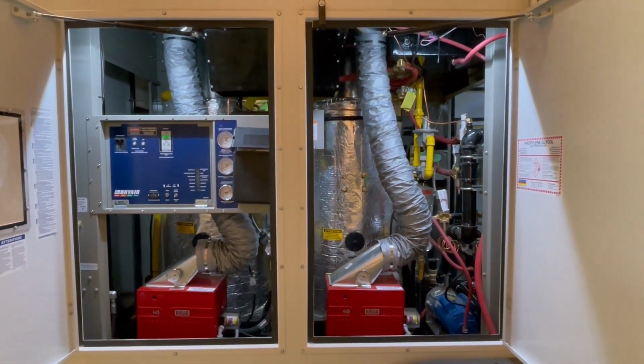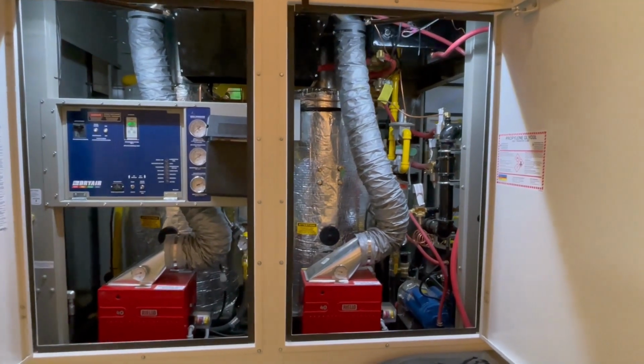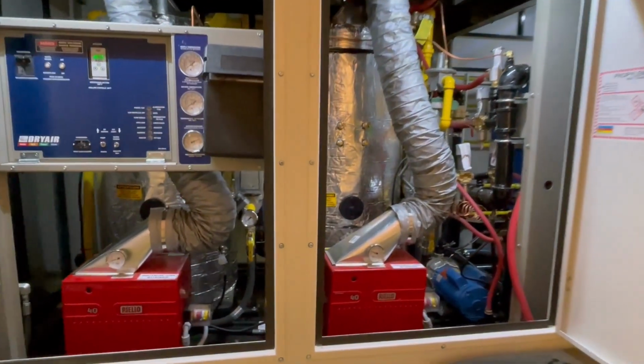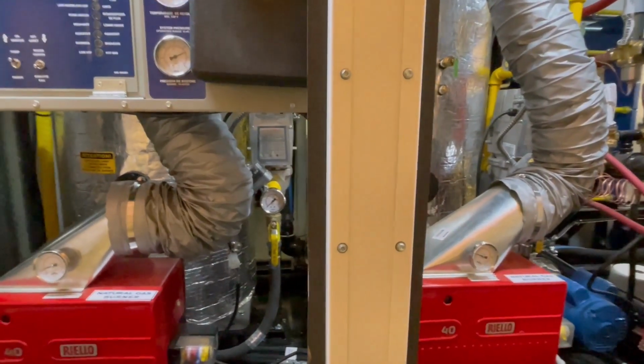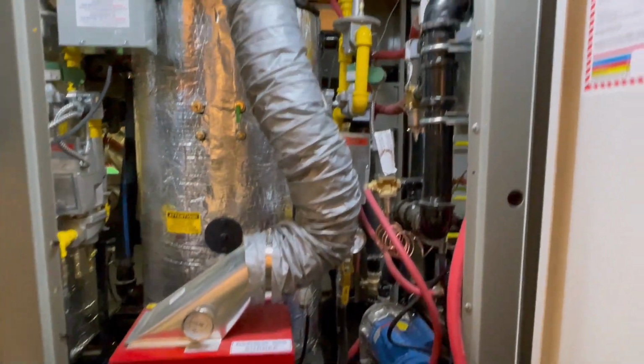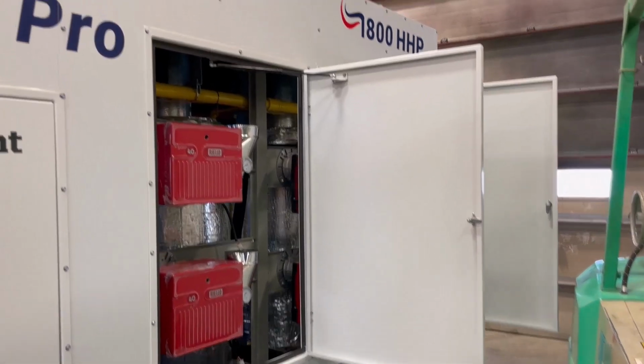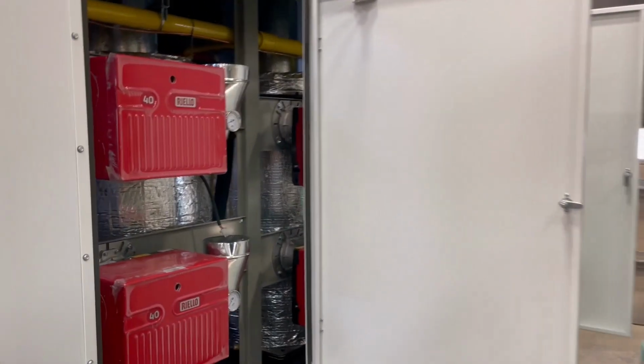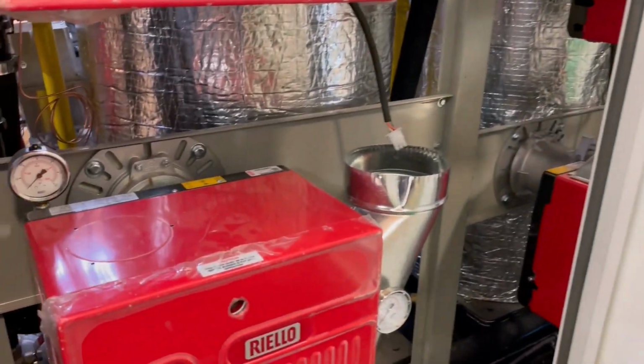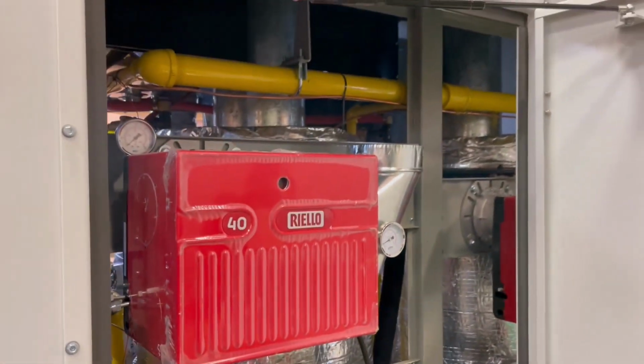The temperature controller is located on the control panel above the leftmost burner, along with any switches to start the unit. Each burner is fueled by its own gas train, with individual gas valves and sensors to be sure each burner is getting adequate gas. On the opposite side of the unit, diesel burners and propane burners are located that can be swapped with the installed natural gas burners when a different fuel type is needed.